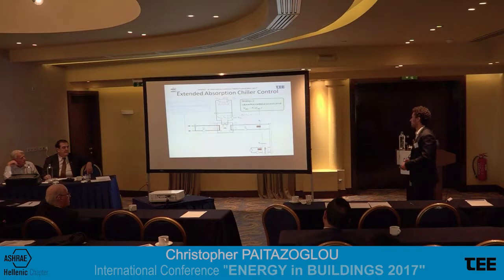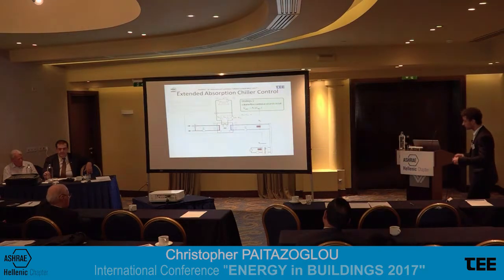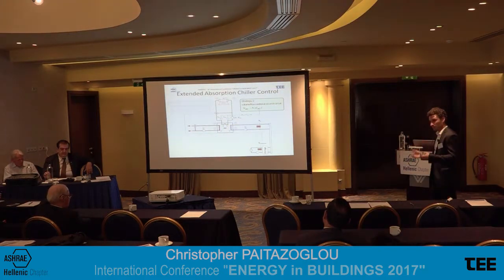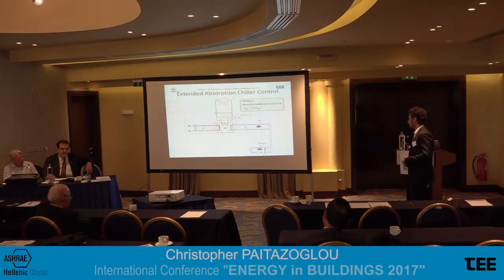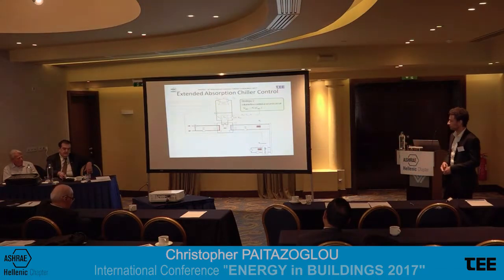Second strategy is changing the flow here by having the goal to operate the pump so that there's a constant temperature difference here. Also, again, in part load conditions. As you will see later, the electricity consumption will be reduced dramatically.